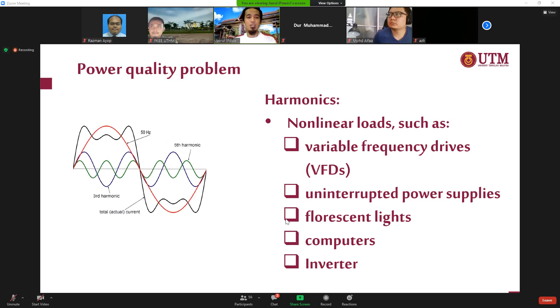So where does this harmonic come from? Actually it comes from nonlinear loads. For example, if we have a variable frequency drive to control the inrush current for a motor, that will contribute to harmonics. An uninterruptible power supply can also inject harmonics, as can fluorescent lights, computers, or inverters. If you recall, I mentioned that when we have a PV we must have an inverter, and this inverter will also inject harmonics into the system. How serious it is, we will see later.